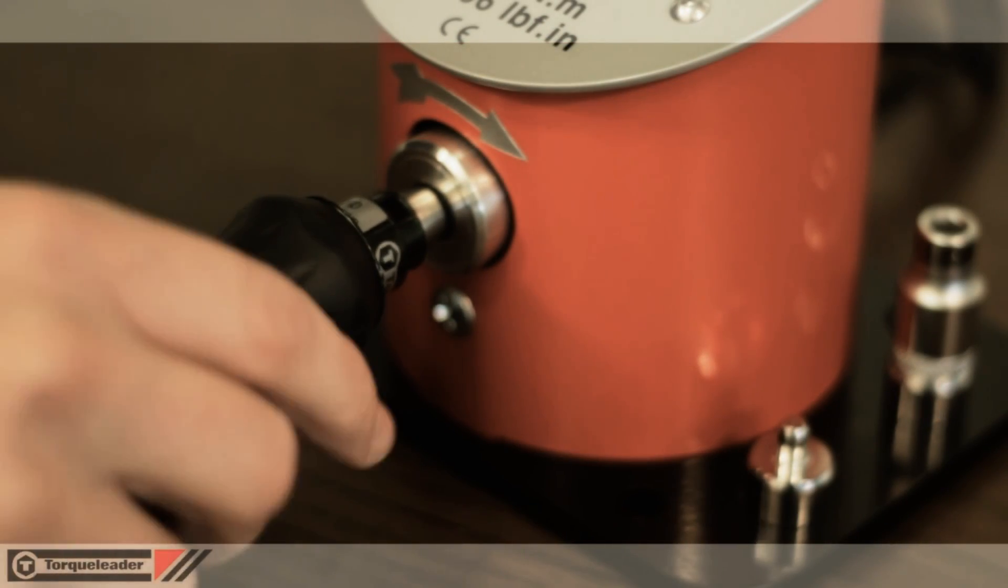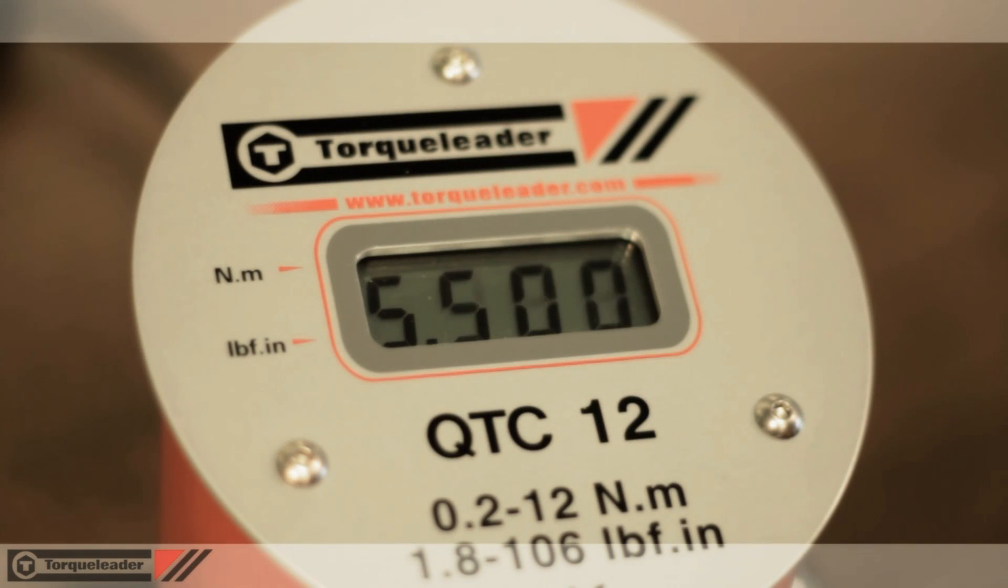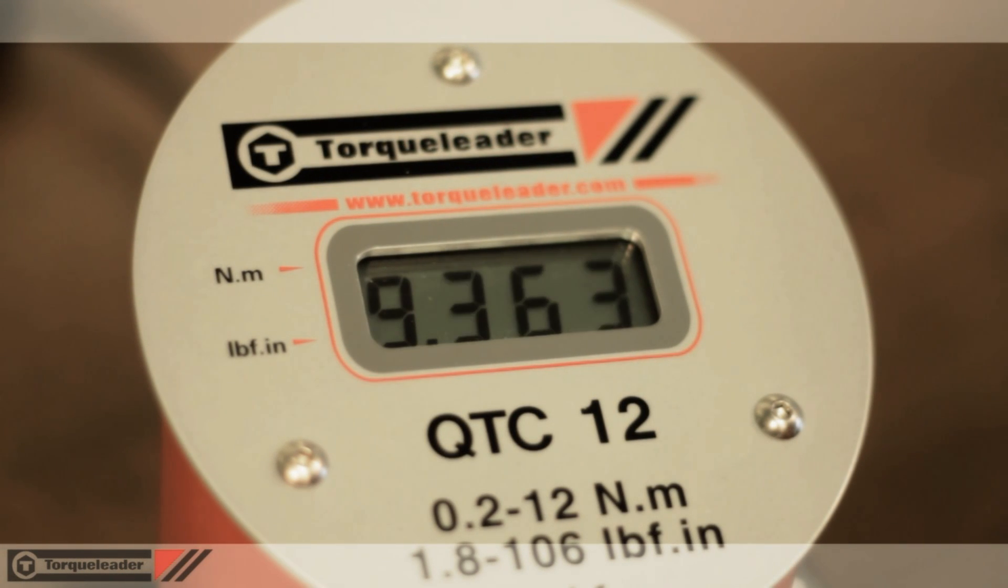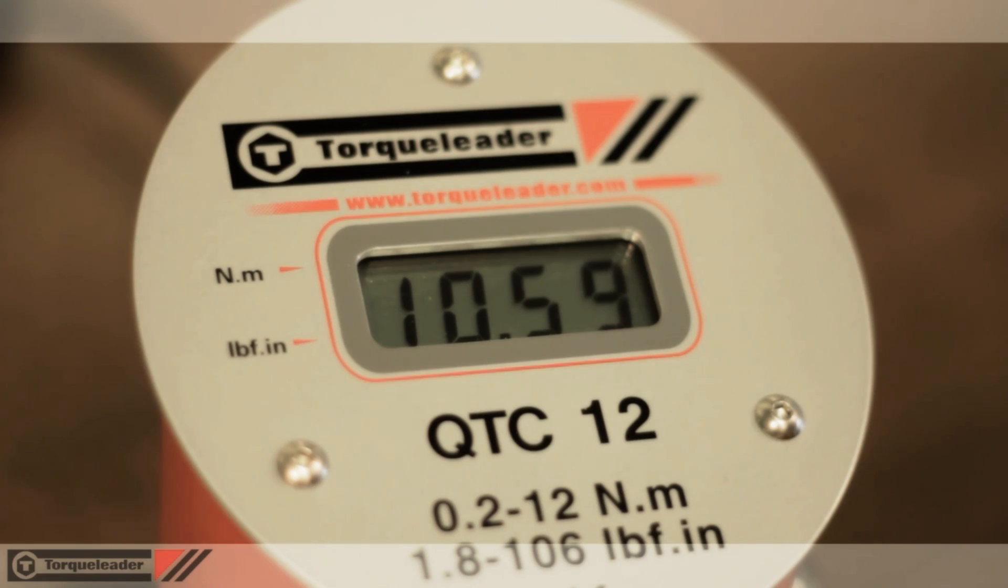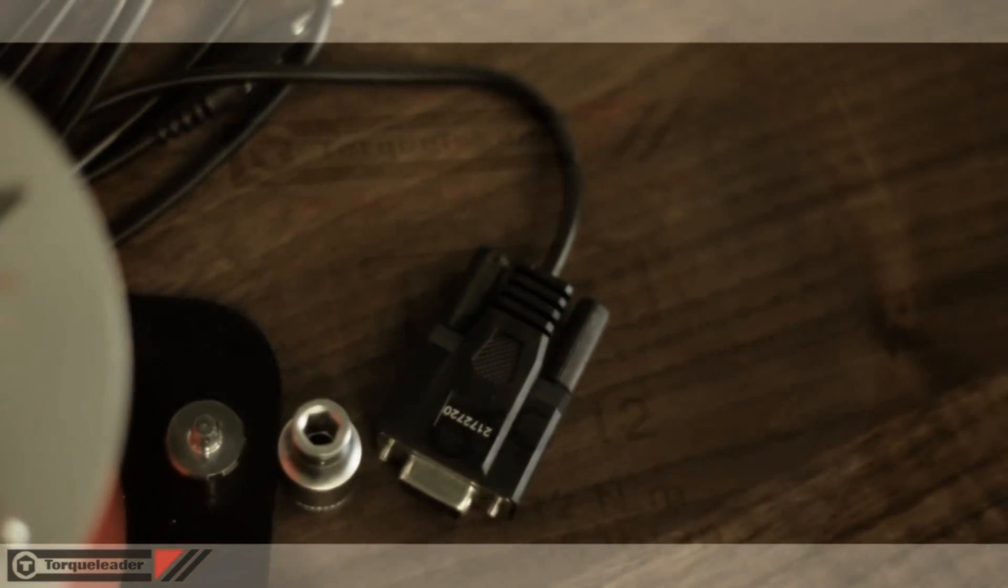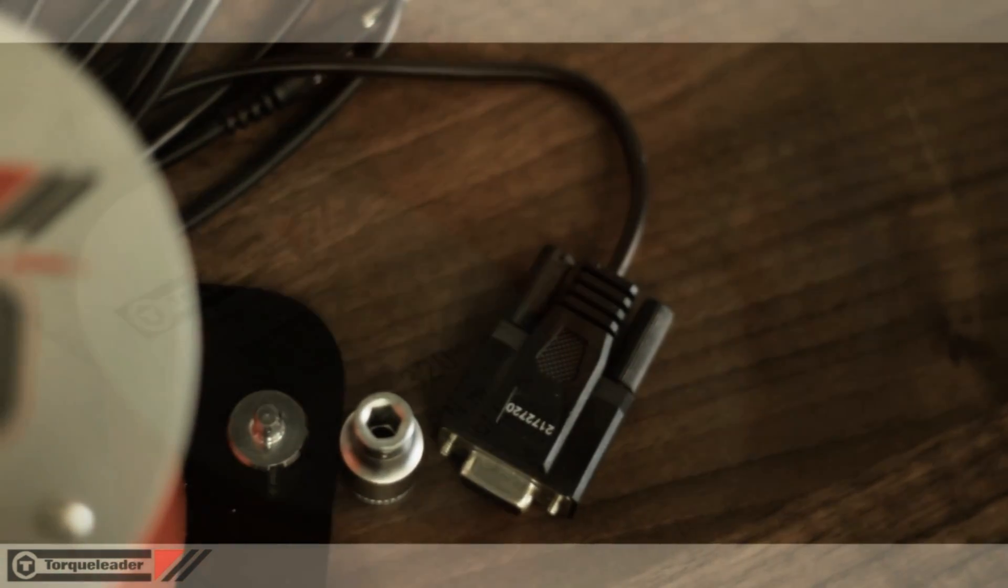Precision setting at low torque values is ensured by the 3 decimal place display resolution. For readings above 10 Nm, the resolution changes to 2 decimal places.